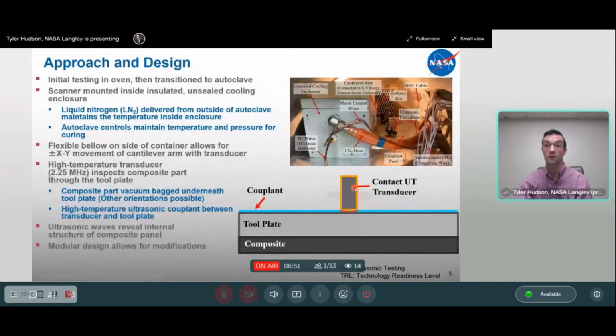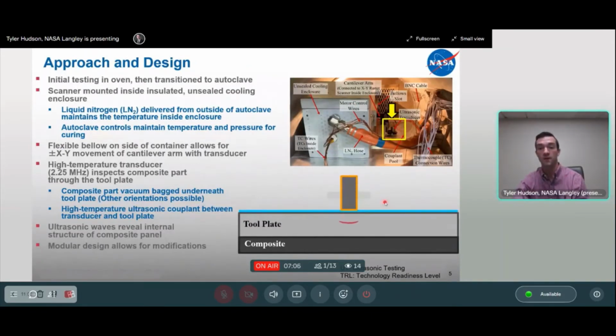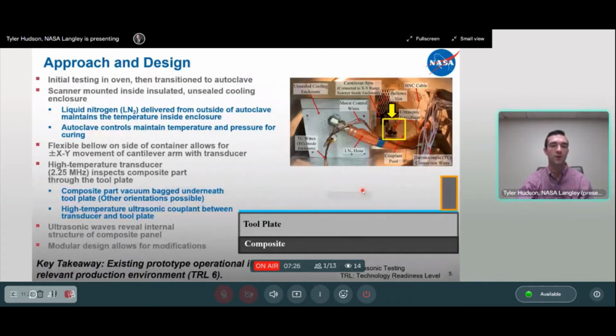So here's a picture of what the system actually looks like. So this is this housing that has all of the electronics. That's what is cooled. Your ultrasound transducer in this configuration is on the tool side. It can be on the part side as well, and it sends ultrasonic waves through the tool plate into the composite, measures that reflection, and then rasters left and right, and then in and out of the enclosure to give you an image of what the internal structure of your composite looks like. And then the key takeaway is that the existing prototype is already operational in a relevant production environment. NASA's TRL for the system is TRL-6.